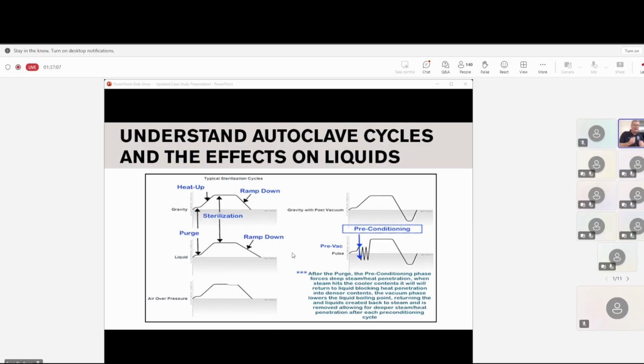So it's nothing hard. It just taps it in every time that steam's trying to push it just a little bit. But if your load is dense, in other words, if you have a bunch of something that is dense and layered, you have to remember what's going on. As that steam goes in there, steam's going to attack anything cold. And what's going to happen when steam attacks cold? It turns to liquid again. So liquid is a barrier for heat. And this is why the gravity cycle is probably not one of my preferences for waste, and for this reason.